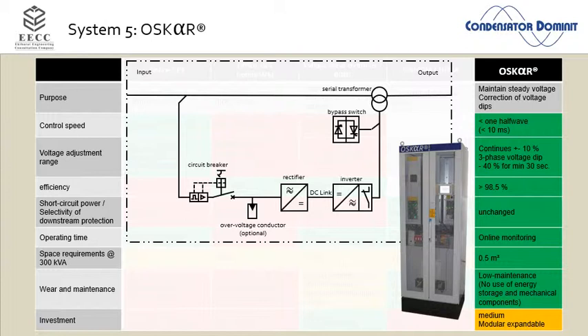So if the voltage drop comes, this inverter is injecting a voltage here. If I inject the voltage here, I have it on the other side as well, obviously with the transformer ratio. I add it to my existing voltage, and the output voltage is exactly 400 volt. Now to do that, this inverter actually has to inject energy into the transformer. Now where does the energy come from? It comes from the DC link.